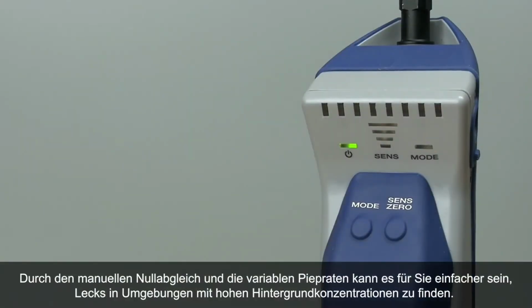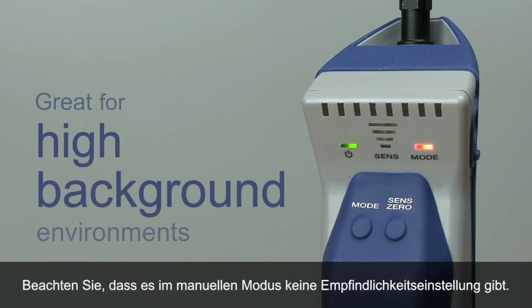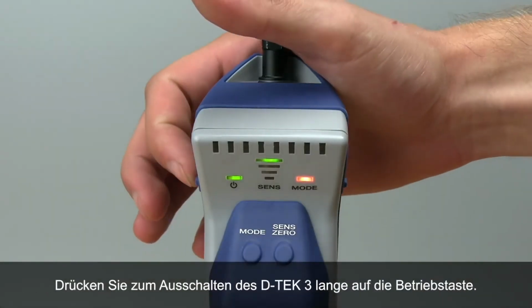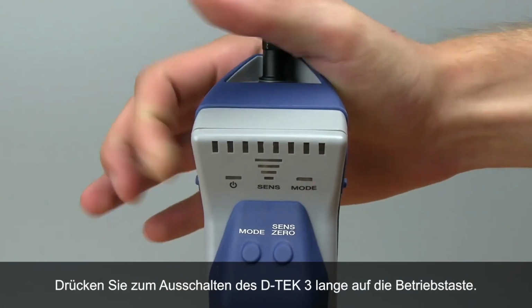The ability to manually zero together with variable beep rates can be helpful for finding leaks in a high background environment. Note that there is no sensitivity setting in manual zero mode. Long press the power button to turn D-TEK-3 off.